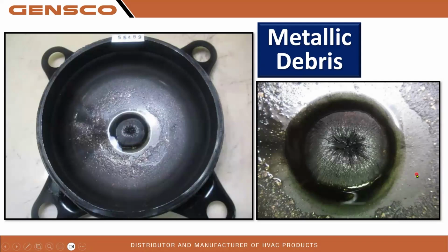Metallic debris from this wear will collect in the bottom of the compressor. There is a small magnet at the bottom of the compressor here. You can see where it has collected steel components. The brass and copper pieces won't stick to the magnet, of course, but you can see how the magnet has collected a lot of steel debris down there. This is a pretty badly worn compressor when you find this kind of stuff.